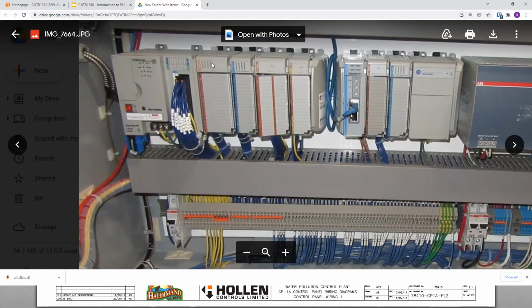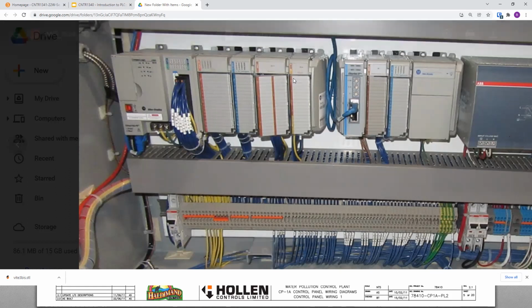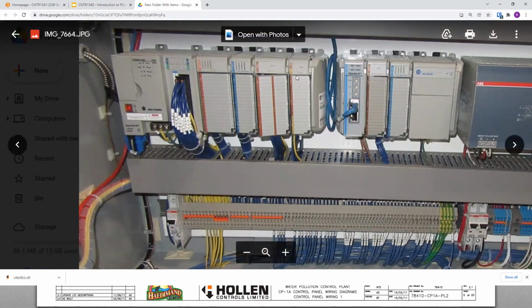I can't tell if that's an input or an output card. I can't tell the color. This one looks brown. I think that one's output, because of the way these lights are arranged. There's 16 points. It could be a relay output card if it's orange. This is brown. This is an analog input card. And this looks like it's an analog input and output card. So to save on IO, sometimes you can get combination cards that do both.